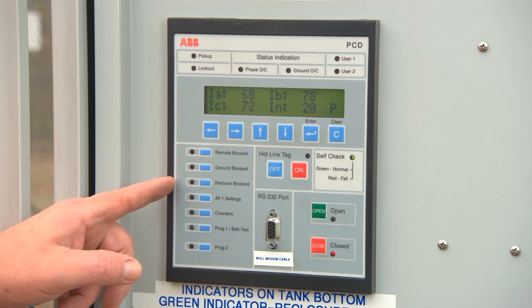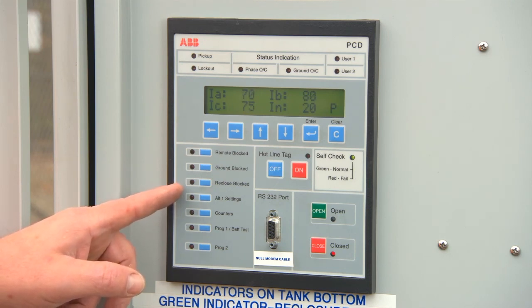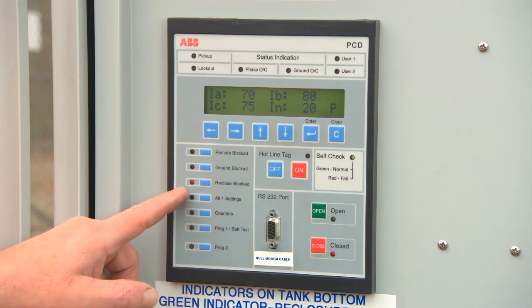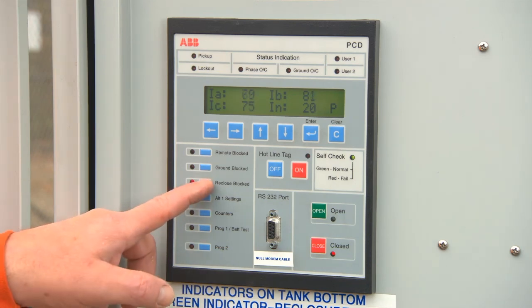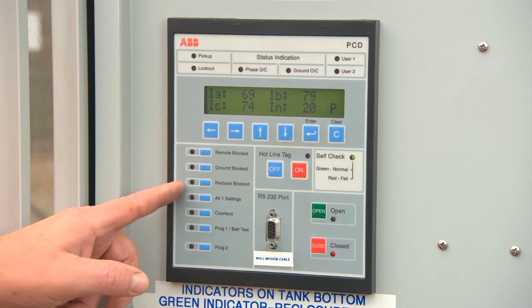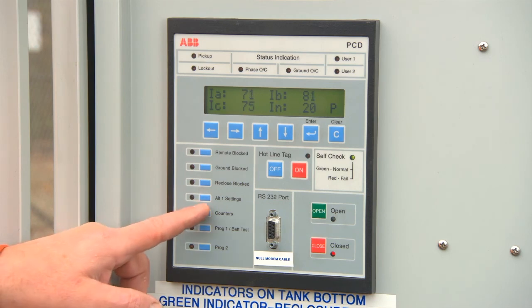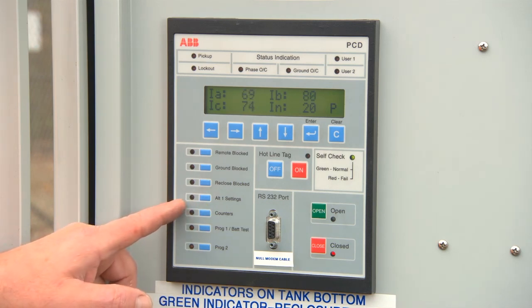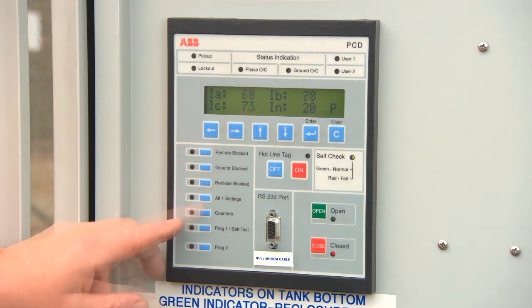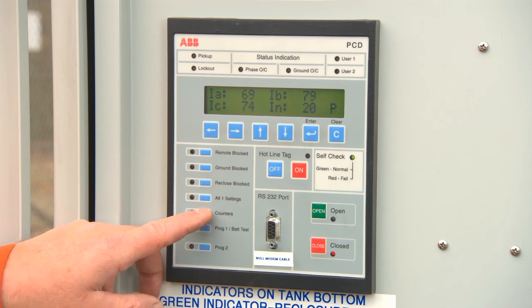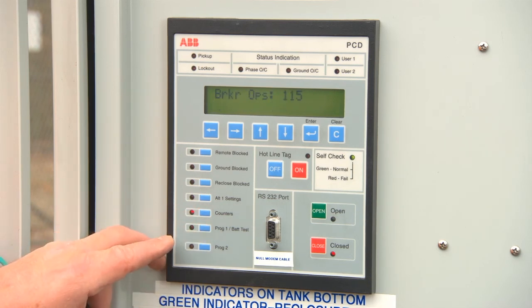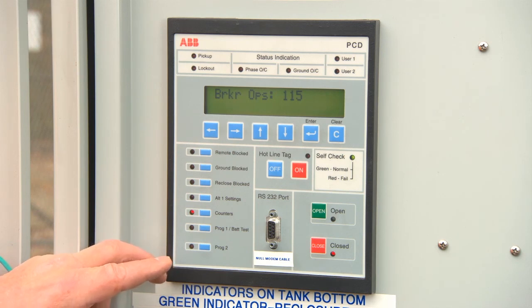Recloser blocked. This feature blocks the multi-shot operation, causing it to only go the one operation before lockout. Press once to turn on. The indicator will turn red. Press again to turn off. You are now back into normal programmed lockout operation. Alternate Settings 1. This will apply a different set of settings to the control for back-to-back setups or various other applications.